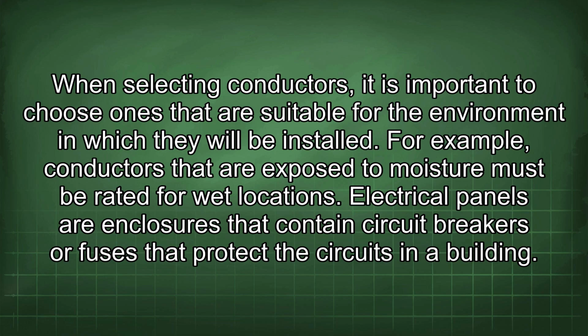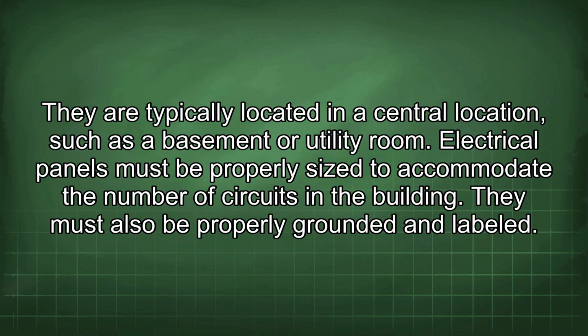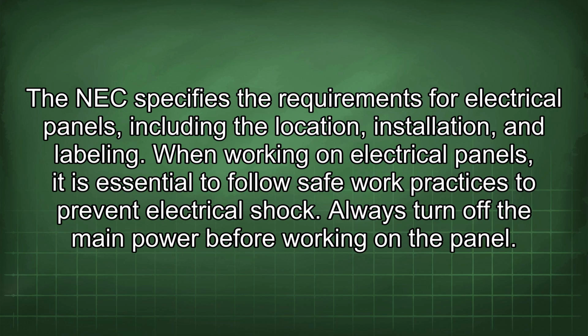Electrical panels are enclosures that contain circuit breakers or fuses that protect the circuits in a building. They are typically located in a central location such as a basement or utility room. Electrical panels must be properly sized to accommodate the number of circuits in the building. They must also be properly grounded and labeled. The NEC specifies the requirements for electrical panels, including the location, installation, and labeling.